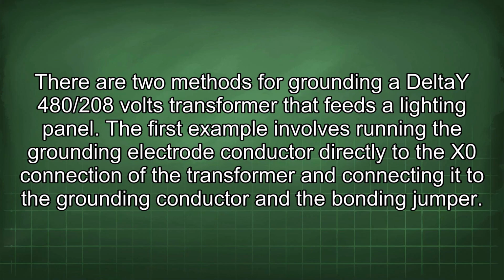There are two methods for grounding a delta Y 480/208 volts transformer that feeds a lighting panel. The first example involves running the grounding electrode conductor directly to the X0 connection of the transformer and connecting it to the grounding conductor and the bonding jumper.